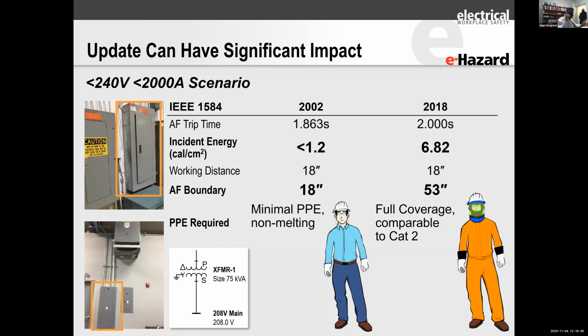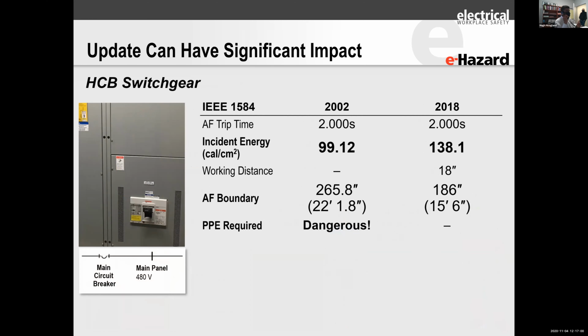So previously we were underestimating the energies. Now, when we rerun the same equipment configurations, where previously we said to folks, hey, this is safe, you don't need to use arc-rated clothing, now we're putting the folks behind at least a level 2 or category 2 type of clothing ensemble. So let's talk a little bit more about this.